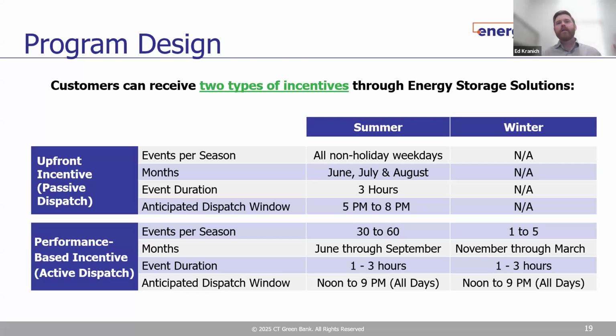So what that means is that in June, July, and August, minus weekends and the two holidays—Juneteenth and the 4th of July—your battery will automatically discharge up to 80% of its capacity to serve your building's load, and any excess will go off to the grid.